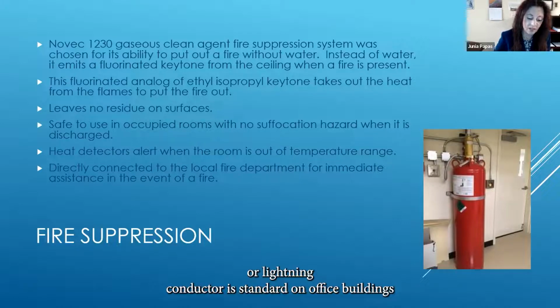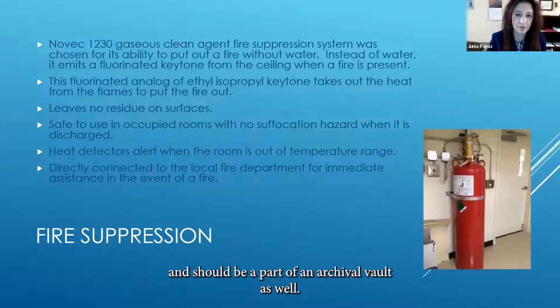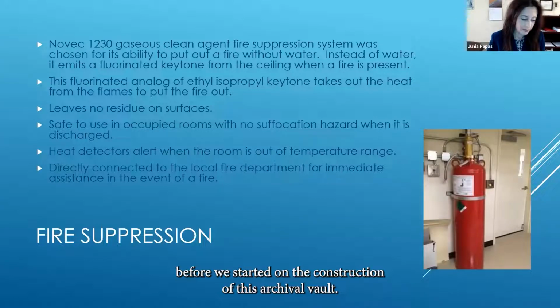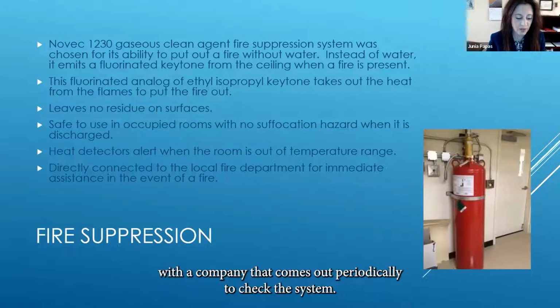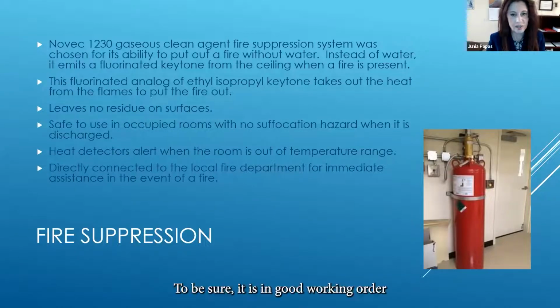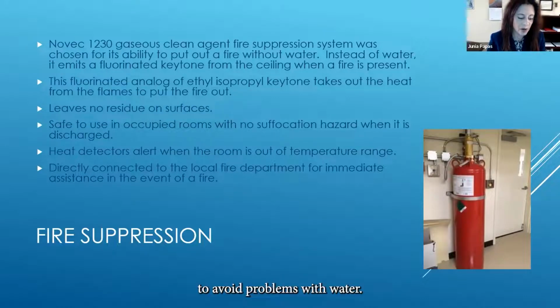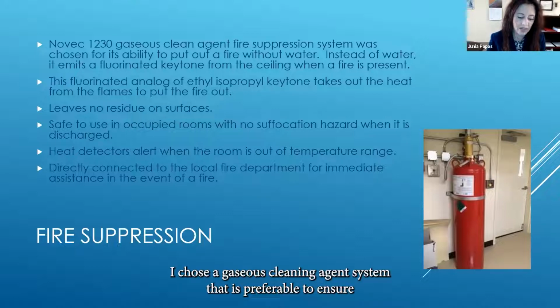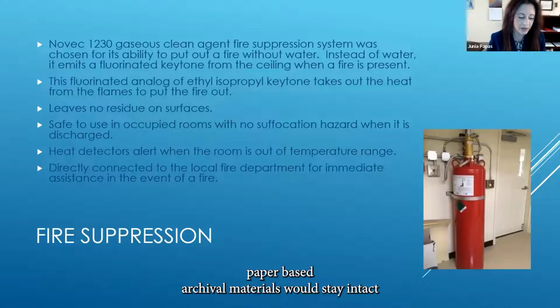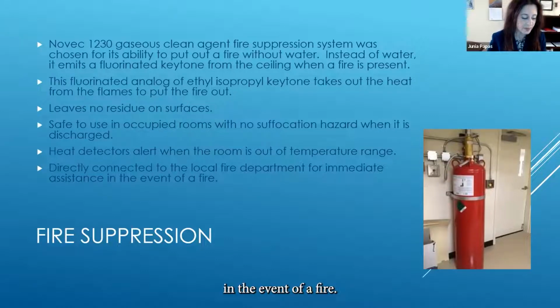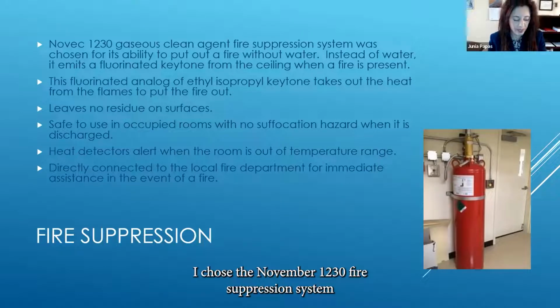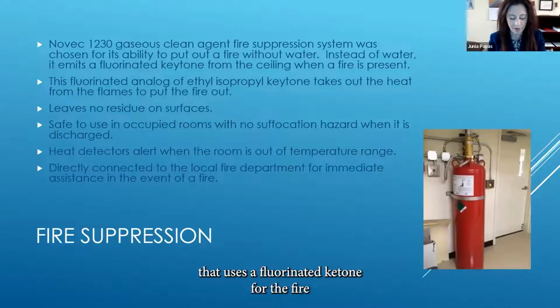A lightning rod or lightning conductor is standard on office buildings and should be a part of an archival vault as well. Our building already was equipped with this before we started on the construction of this archival vault. Fire suppression systems should always be maintained under contract with a company that comes out periodically to check the system to be sure it is in good working order. To avoid problems with a water sprinkler system, I chose a gaseous clean agent system, which is preferable to ensure paper-based archival materials would stay intact in the event of a fire. So instead of water sprinklers at the ceiling, a gaseous clean agent system has pipes and diffusers that have a proprietary gas within them. In the event of a fire, this gas is dispersed in the room without leaving a residue. I chose the Novec 1230 fire suppression system that uses a fluorinated ketone for the fire suppressing agent.